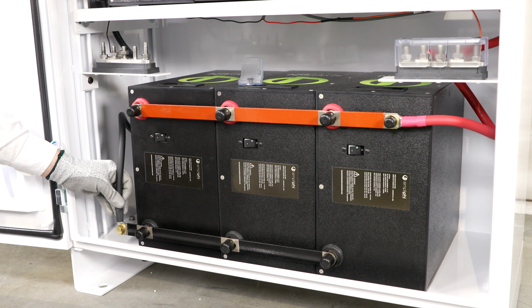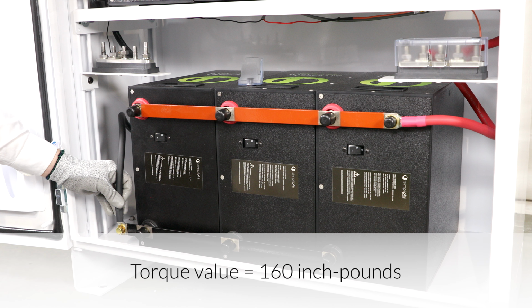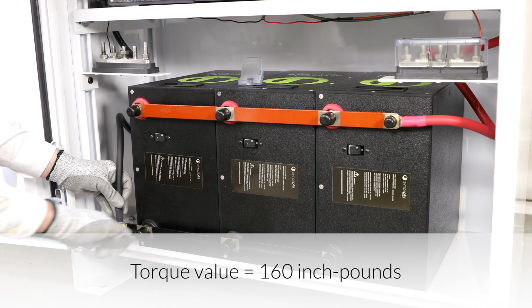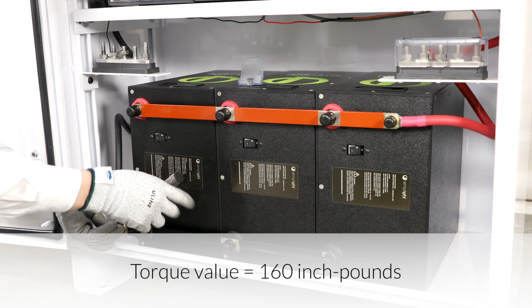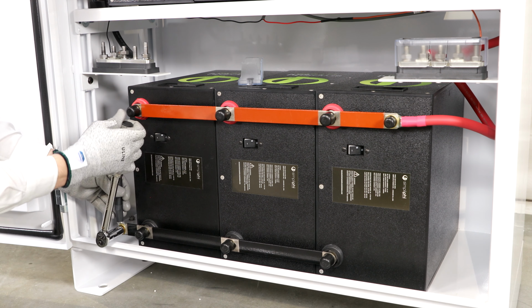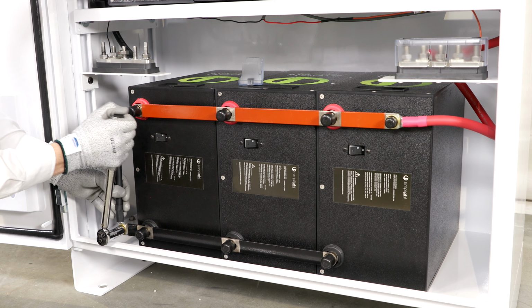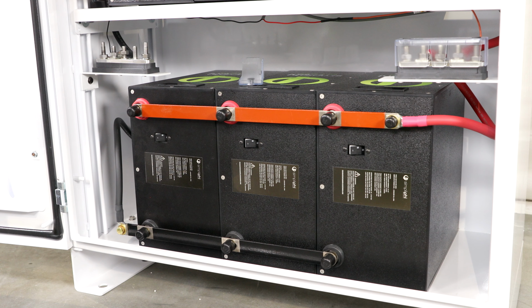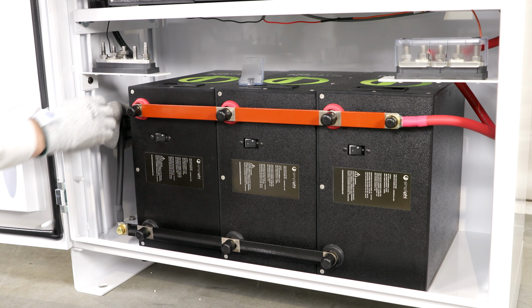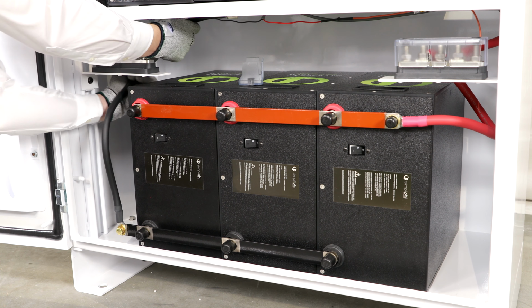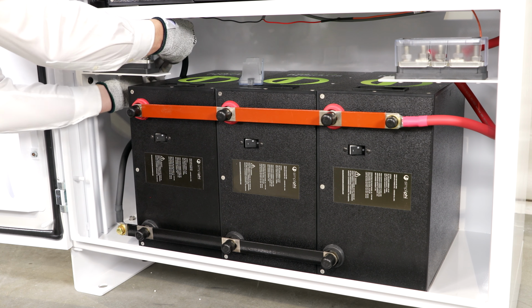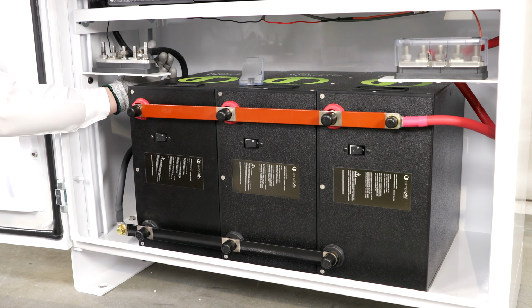Now, secure the cable lug to the bus bar by tightening the brass hex head cap screw to 160 inch-pounds of torque. While tightening, secure the lug with the other hand so that it doesn't twist or move. Route the cable from the bus bar to the 5-point terminal block directly back and up to the 5-point terminal block.